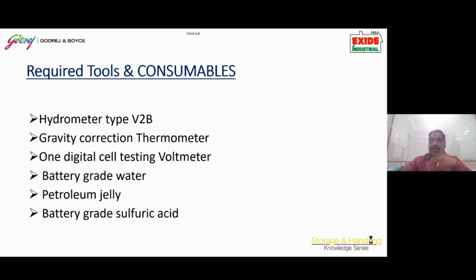Sulfuric acid should never be added as a top up. In fact, it should only be used under the guidance of the OEM, and this can only be done if the battery has to be completely revived, all the cells taken out, the electrolyte removed, and new electrolyte put in after repair. Secondly, only in case of transit, whenever there is loss of electrolyte due to topping up, falling from the truck, or any damage causing electrolyte loss, in those cases only should sulfuric acid be added, and it should be done only in consultation with the OEM and strictly in the presence of the OEM.